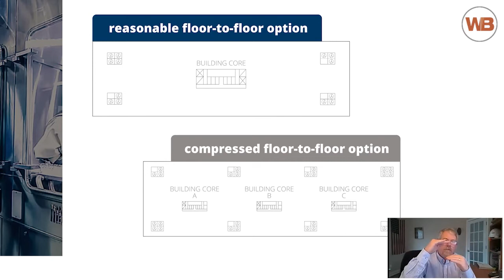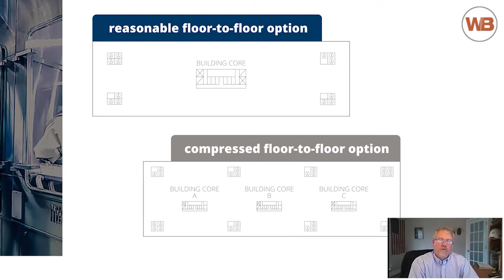The real advantage is that with a tighter floor to floor, you're cutting the ducts in half or by two-thirds in some cases, reducing the total floor to floor you need to convert to lab space. It's tight for flexibility and adaptability, but it is a doable and feasible solution - as long as you understand the costs and the space you're giving up for additional shaft space. So there's pros and cons, but it's a feasible strategy.